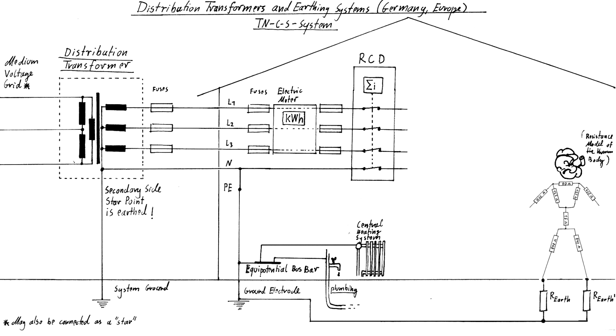Fuses melt when their rated current is exceeded for a certain period of time. That condition can be caused by a very low load impedance, or in the most extreme case, by a short circuit, where at least two conductors are in direct contact. If there was, for example, a short circuit between one of the phases and the neutral right here, this fuse would blow, separating the circuit and preventing overheating and possible fire in the transformer or the line.